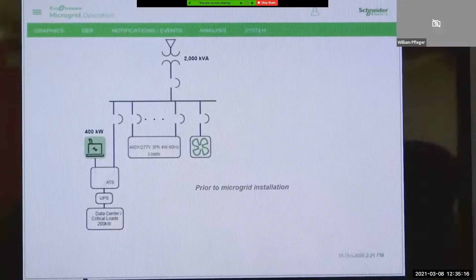And that way, even if the utility goes down and it takes a few seconds to bring up the generator, the data center and critical loads never even see a blink thanks to the UPS. Okay? Now, one thing you may notice here is 400 kilowatt generator, and we only had 200 kilowatts of data center and critical load. And with this setup, there's no way to use that extra capacity of the generator. That extra 200 kilowatts of capacity has no path to any of these other loads.